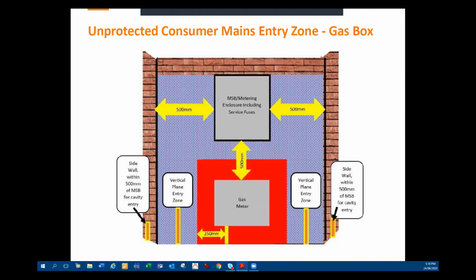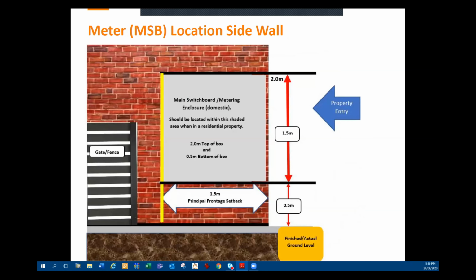And just the next slide across. Right here we have a switchboard, and you're stating that the bottom of the switchboard has to be no lower than half a metre high. What about a ground mount switchboard? Yeah, so this is basically as a meter box located on a side wall. The intent there is so that it's at a standard height for a type 1 or a type 2 board. If it becomes a ground mount switchboard, then it's basically the bottom of the meter panel area, and the general switchboard is within that half a metre up to 2 metres.